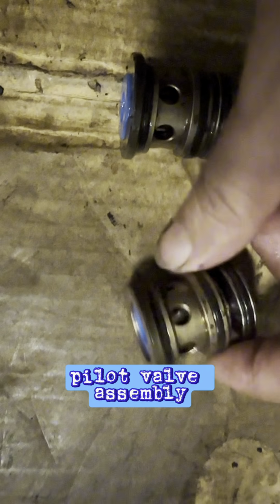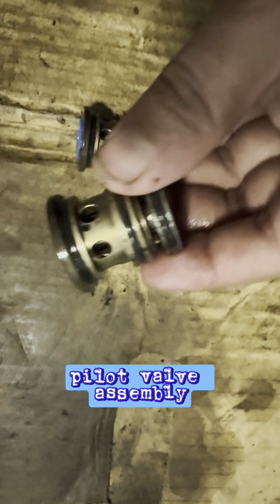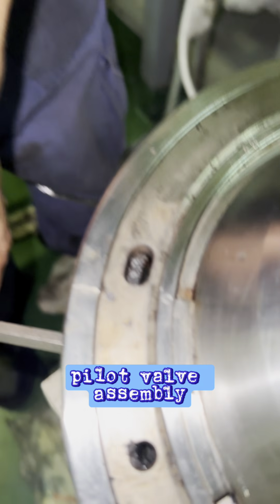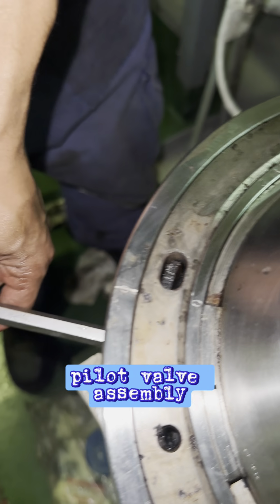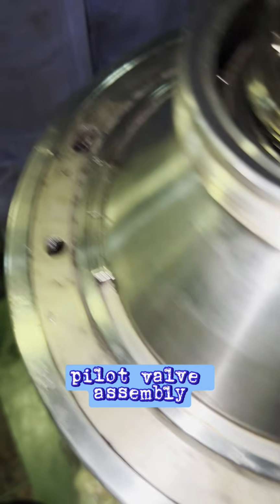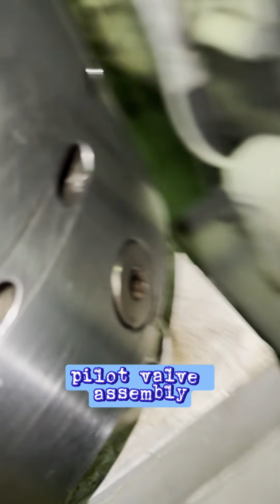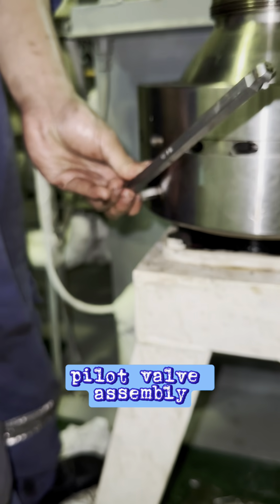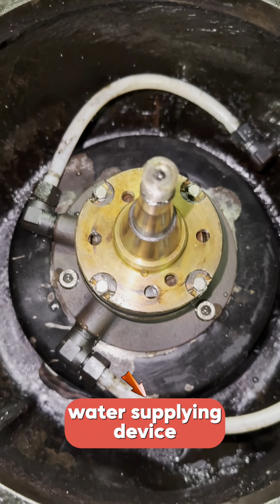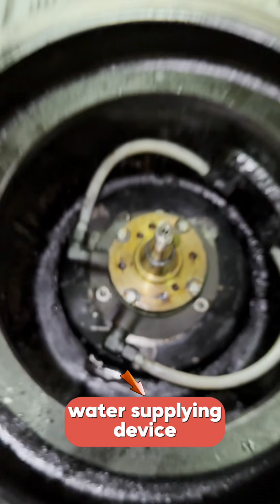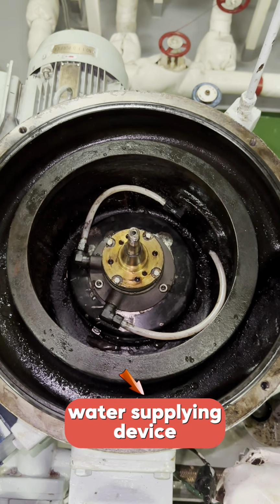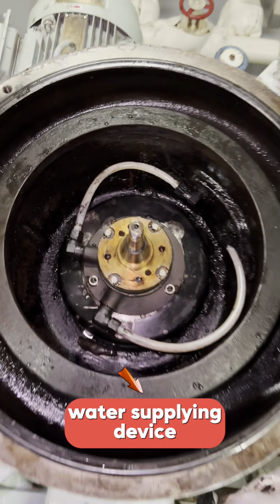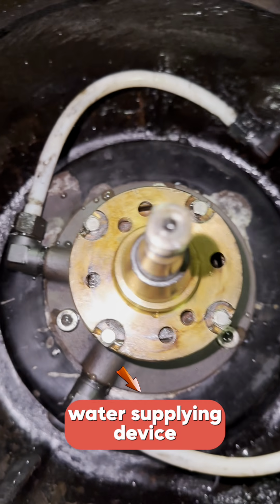The main cylinder closes the bowl when the pilot valve assembly is in closed position. If the pilot valve assembly opens, the main cylinder will slide vertically down, opening the bowl and will allow the discharge of accumulated sludge. The water supplying device assembly. It is positioned under the bowl to supply the required amount and pressure of operating water for opening and closing the bowl.